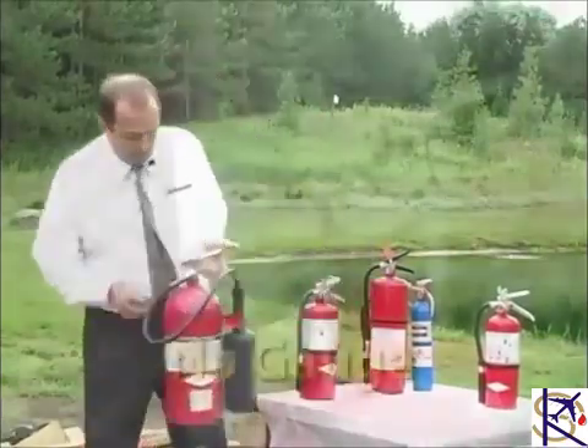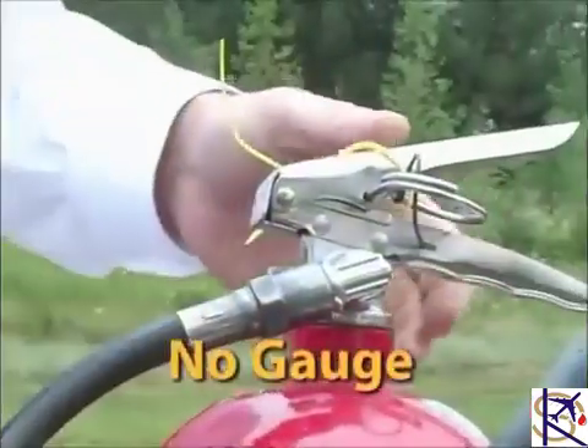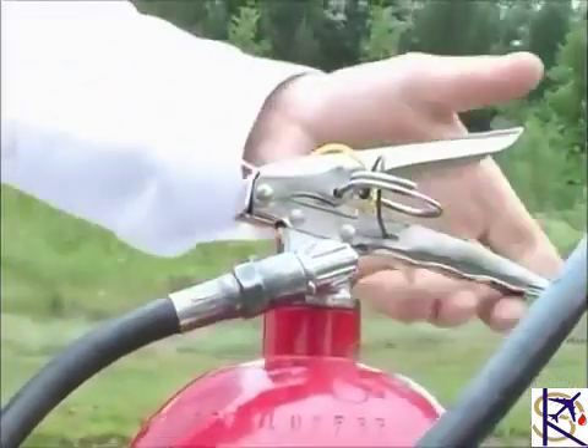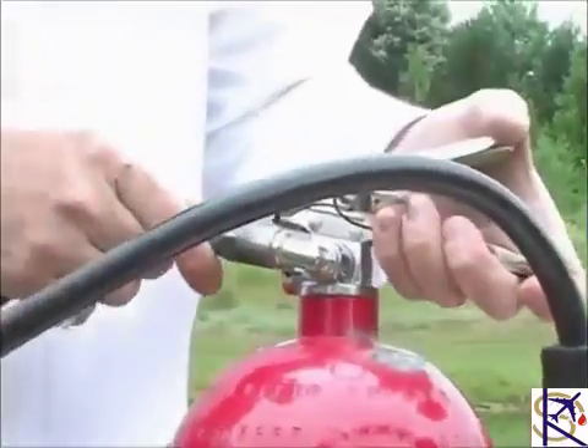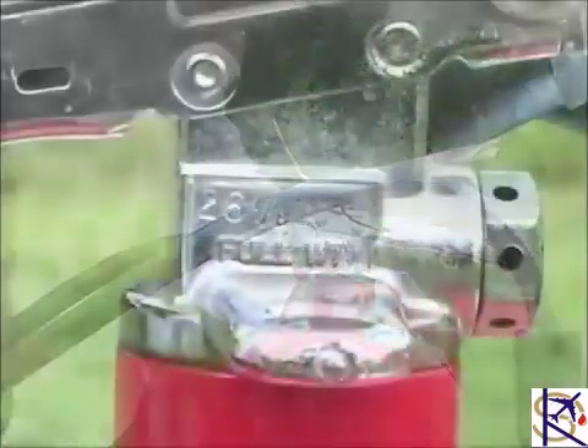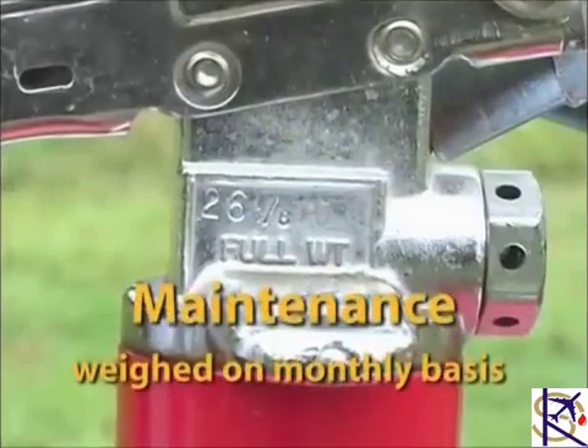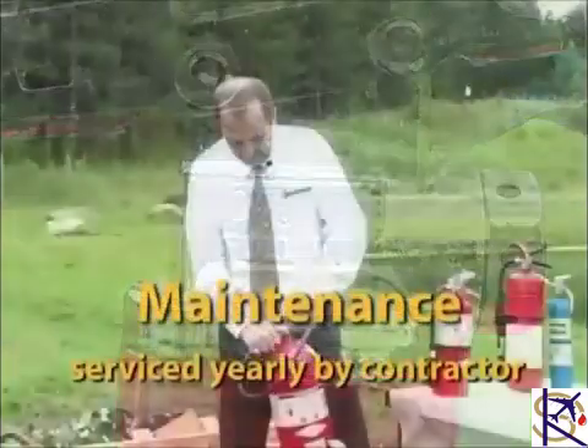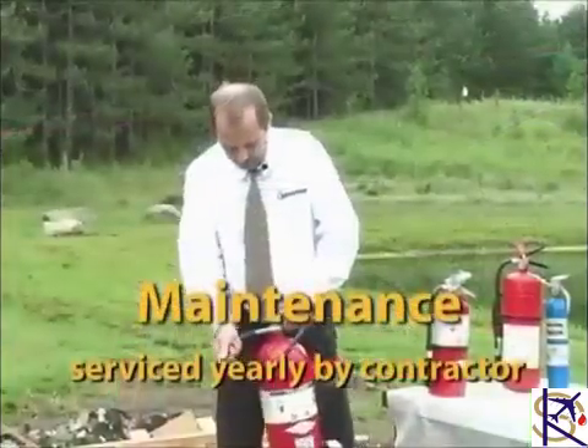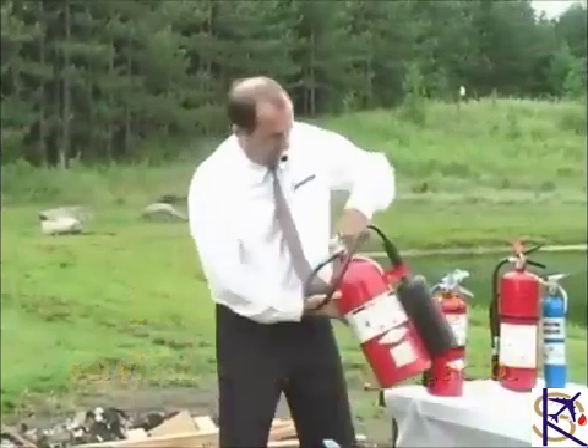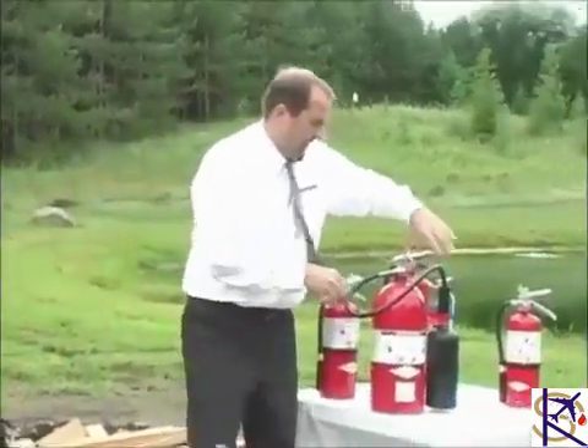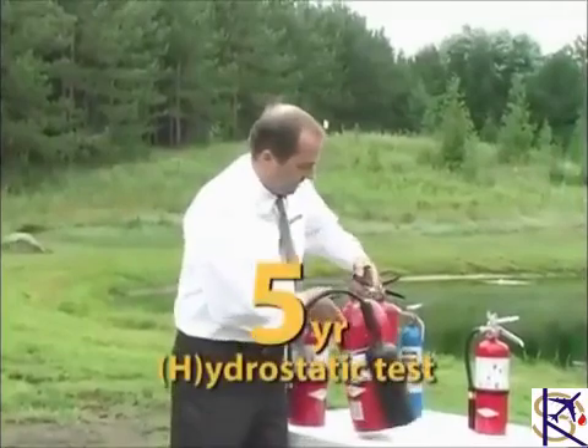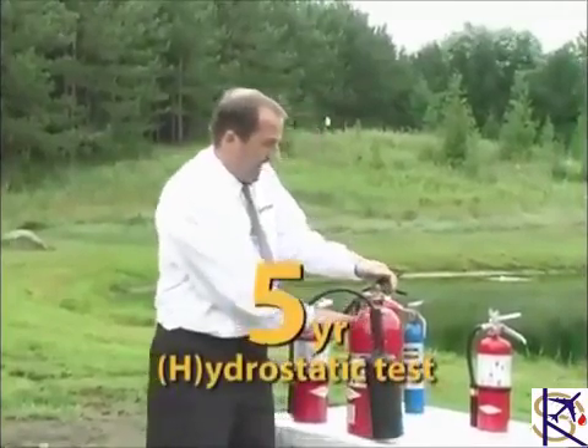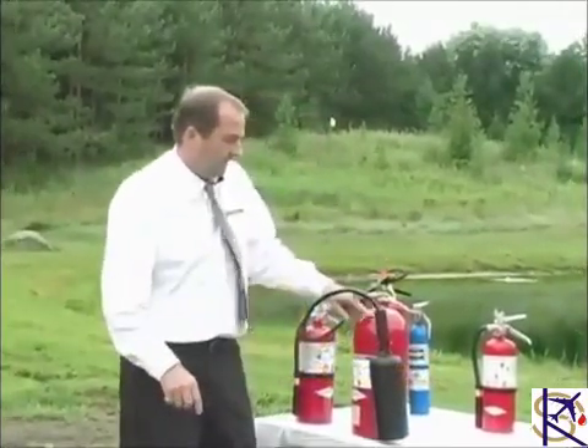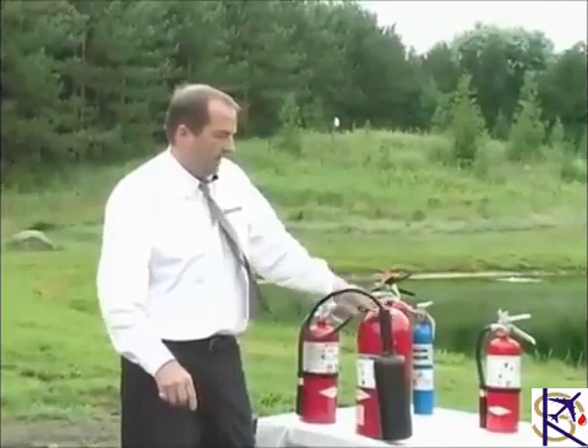Notice there's no gauge, and the only way you can tell that it's full is by the weight of the extinguisher. So it needs to be weighed on a monthly basis, and on a yearly basis, again weighed by an outside contractor. These particular extinguishers need a 5-year hydrostatic test from the date of manufacture, which is stamped on the cylinder. High pressure cylinder.